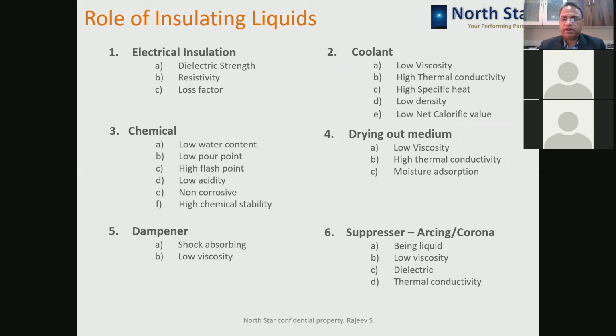Then, being a viscous liquid, it acts as a dampener, that is, a shock absorber. So any forces or impacts coming on the winding are absorbed by the oil, and it is an excellent arc suppressor. So it helps in quenching any fire or any arcing inside the transformer.